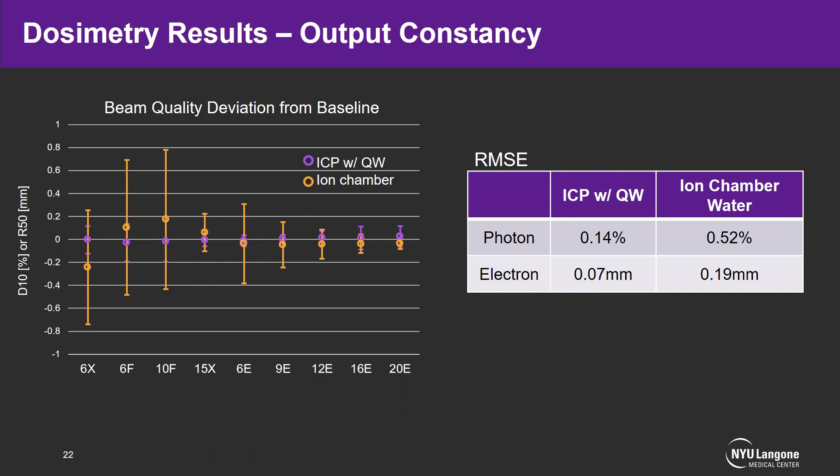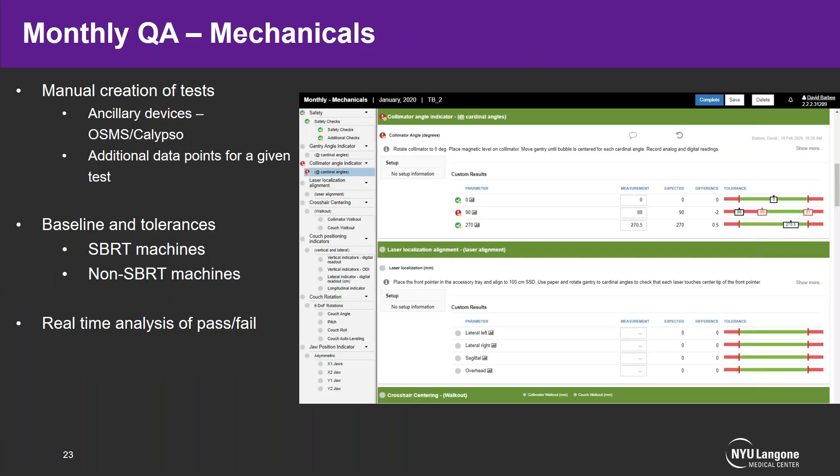We also looked at energy output constancy, examining D10 percentage change or R50 depth change across all machines and energies. The IC Profiler and quad wedge were much tighter than the ion chamber in water, and the repeated root mean squared error calculation again confirmed that the IC Profiler and quad wedge were significantly lower than ion chamber in water.